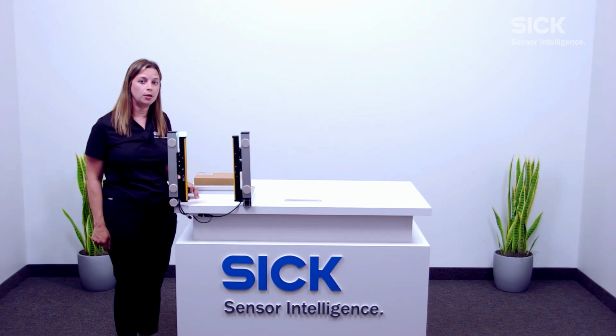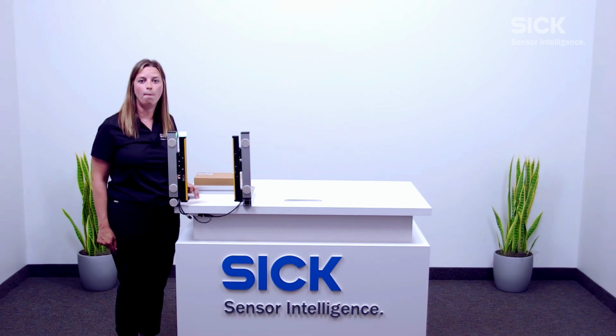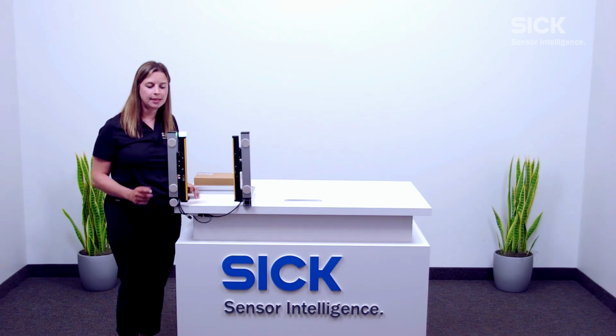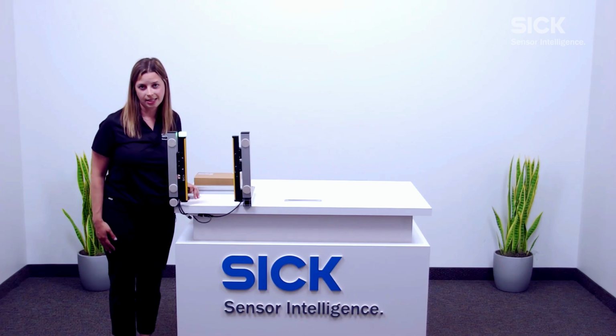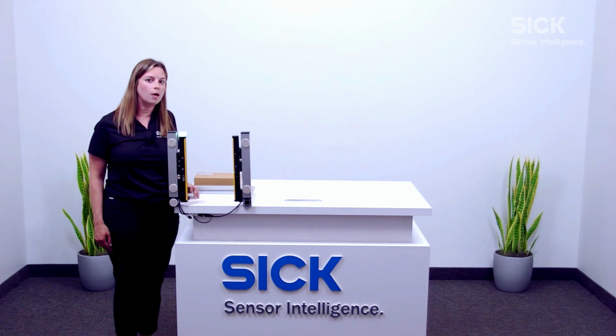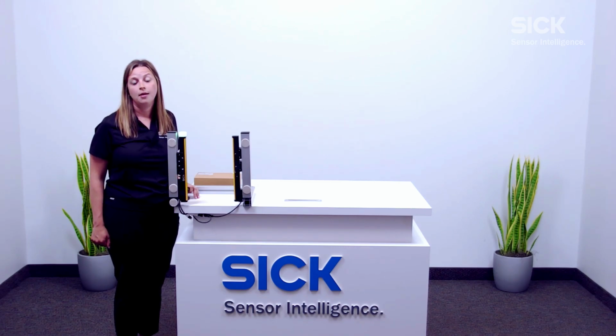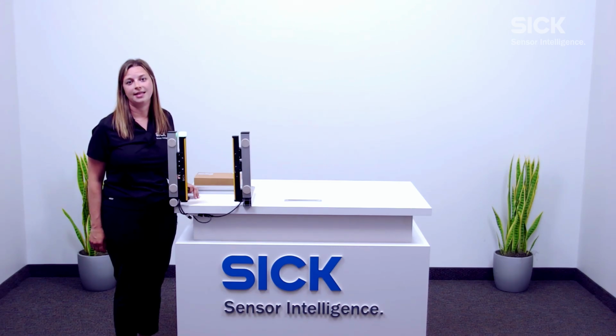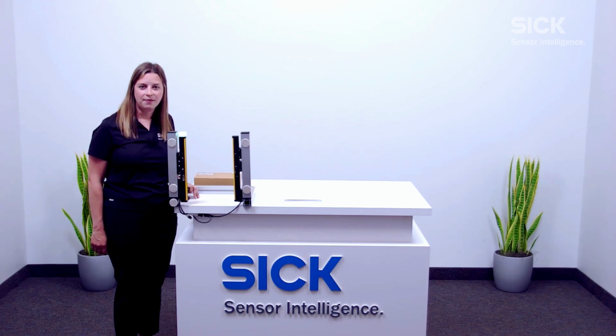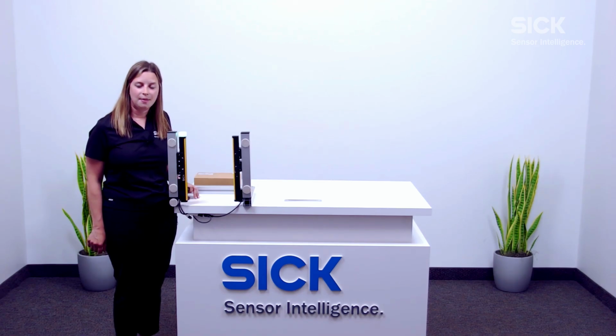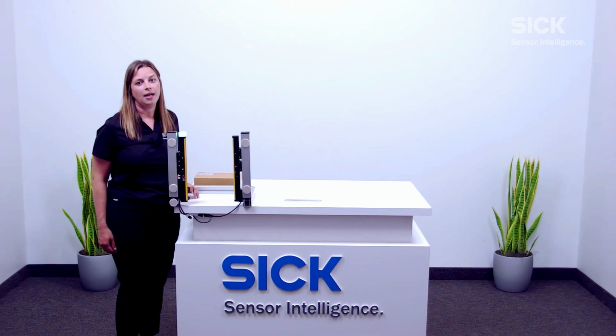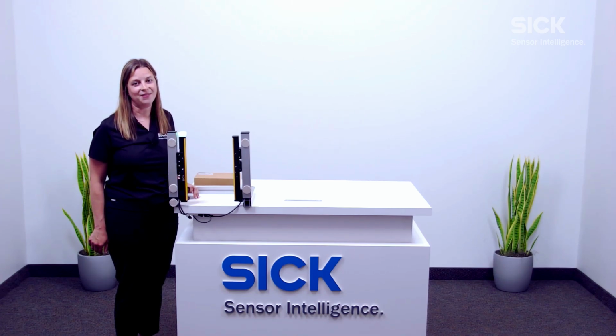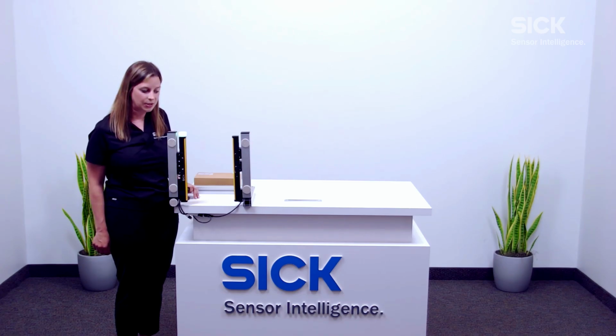With this, it's important to note that we need to have a light curtain that has firmware version 1.1 or newer. This can be found on the back of the light curtain next to the part number. Overall, smart box detection is a great way to increase your machine uptime and improve overall process productivity, allowing you to safeguard areas that may, in the past, have been difficult to safeguard. It alleviates the need for having muting sensors, and so that makes it even easier to initiate and install.